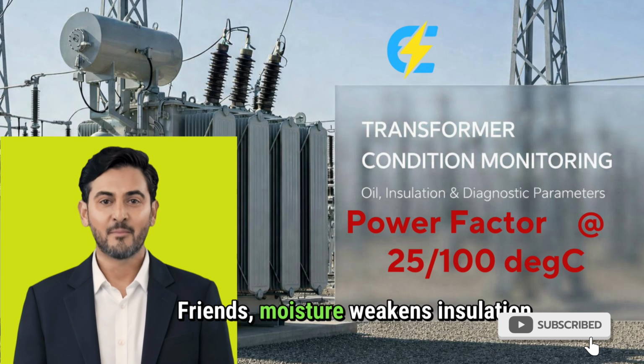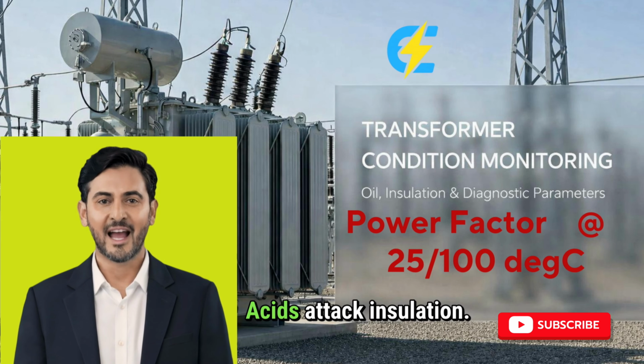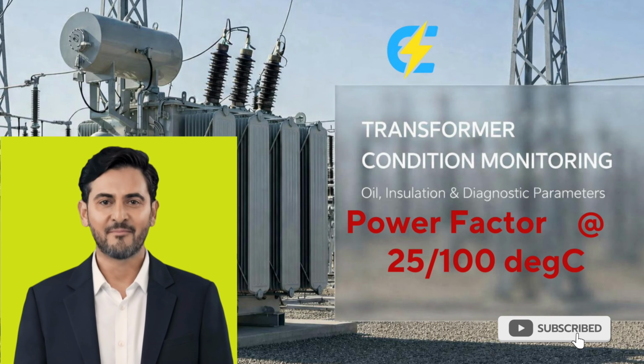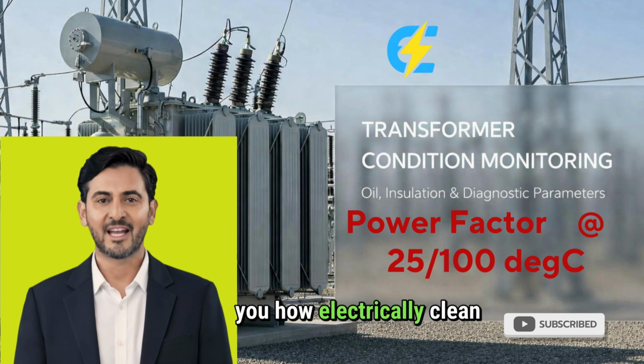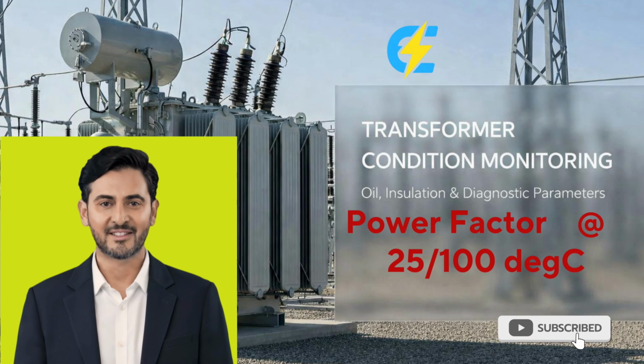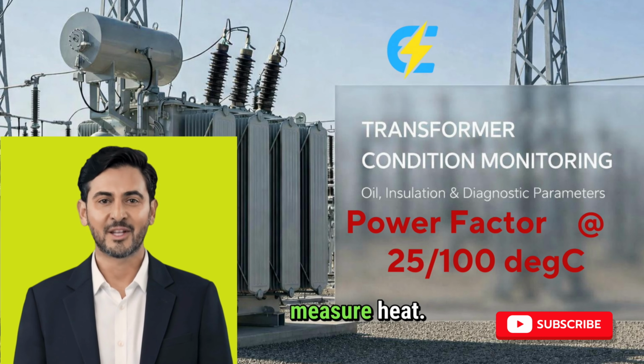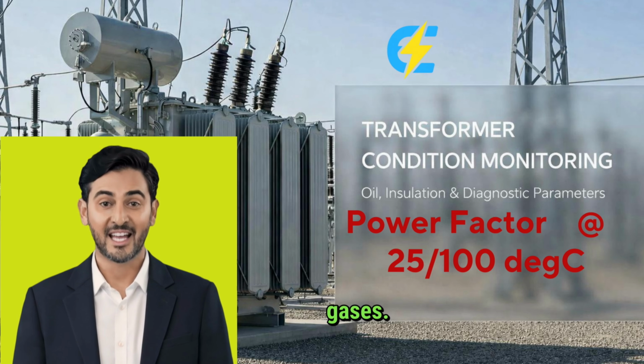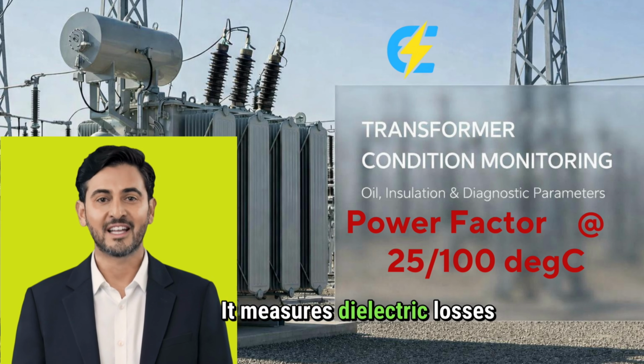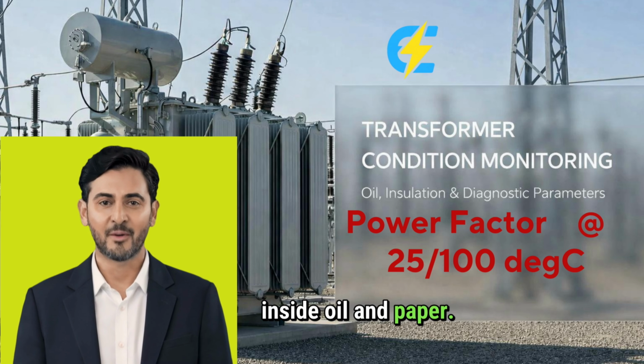Friends, moisture weakens insulation. Acids attack insulation. But power factor tells you how electrically clean the insulation really is. Power factor does not measure heat. It does not measure gases. It measures dielectric losses inside oil and paper.